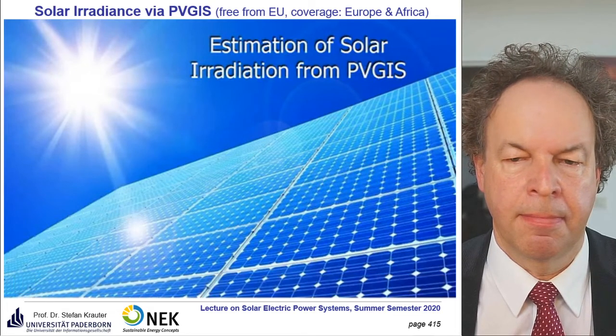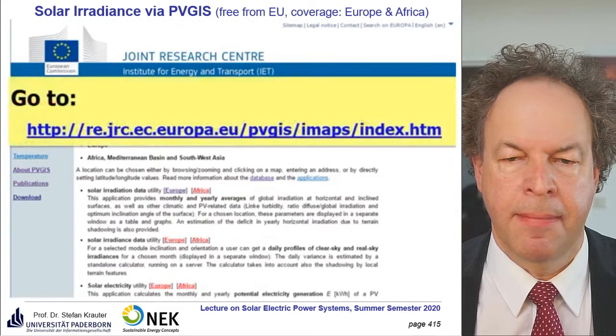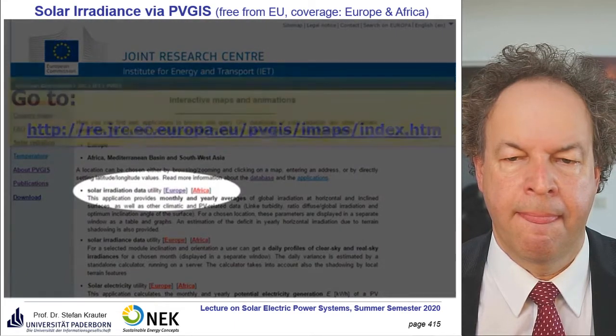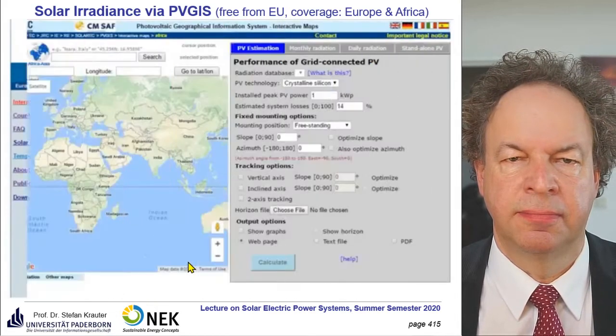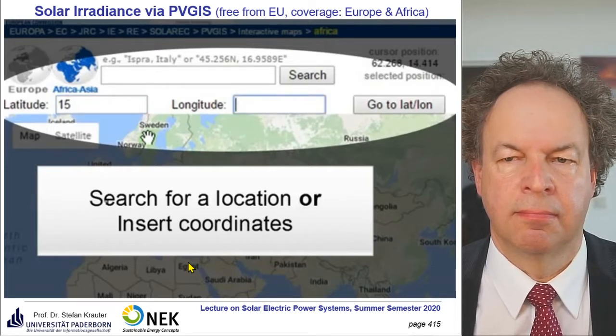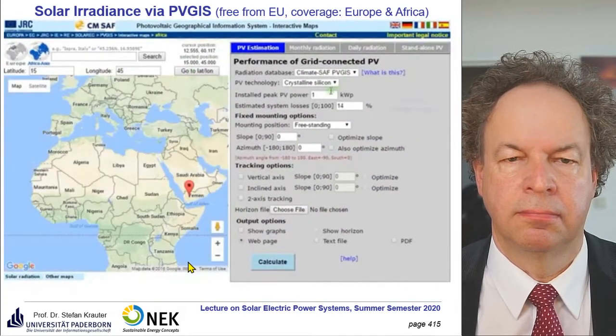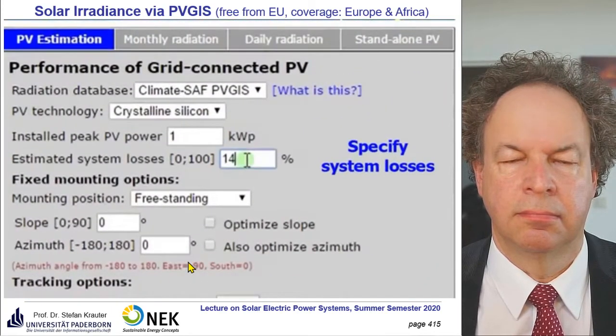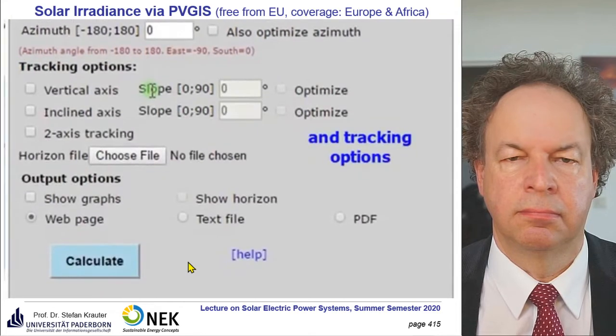In this video I will show you how to estimate solar irradiation using the PVGIS database. Go to the PVGIS website and click either Europe, or Africa and Asia. We will choose Africa and Asia. You can either search for a location or enter latitude and longitude — we will enter a location in the Middle East with 15 degrees latitude and 45 degrees longitude. In the PV estimation tab you can assess the performance of a grid-connected system, specifying system losses, tilt angle, orientation, and tracking options.